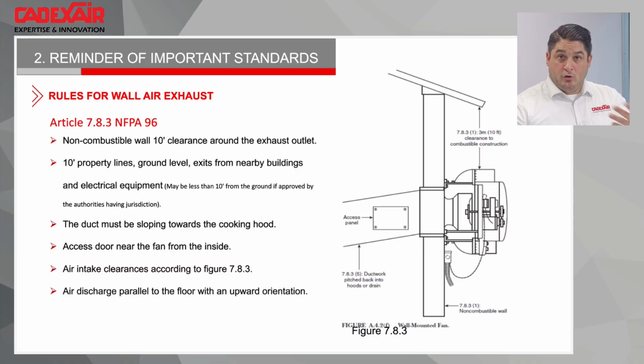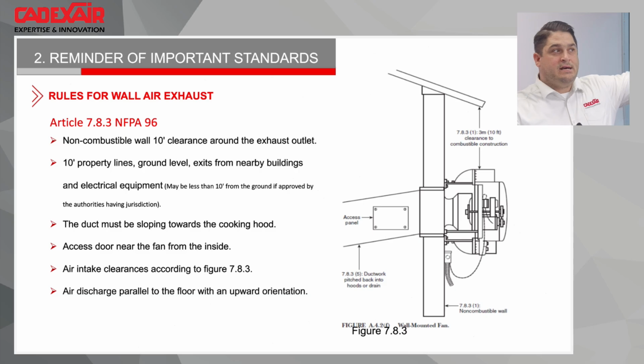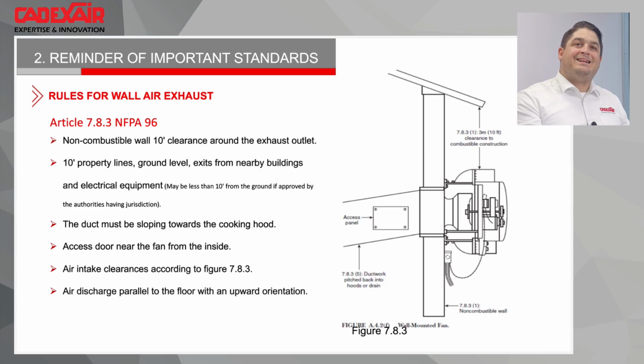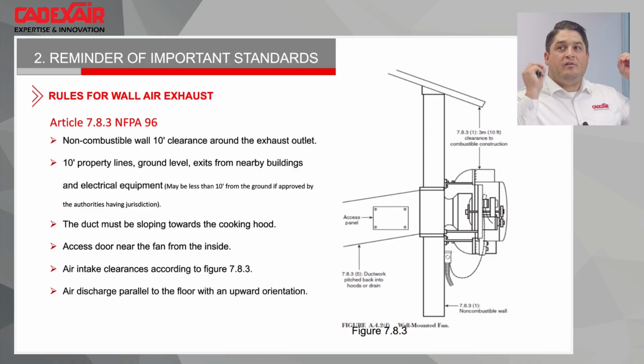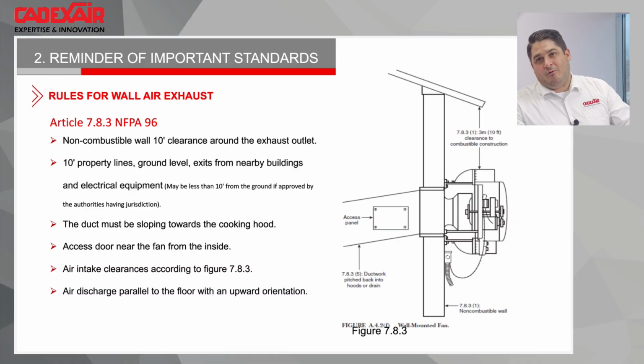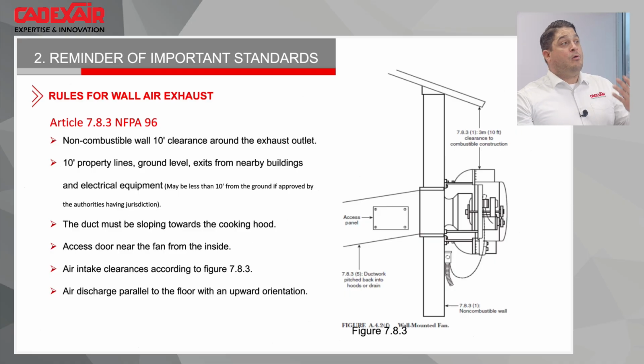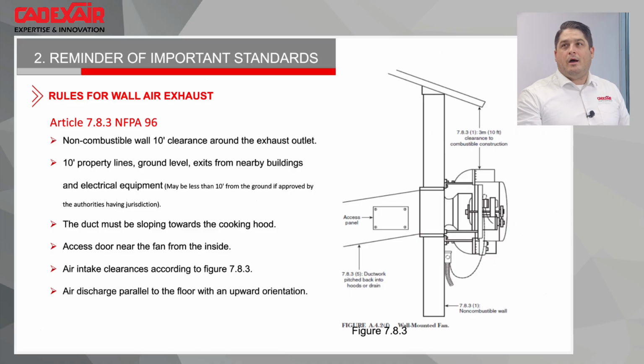Also, when you work with a louver on a wall discharge, you need to exhaust parallel to the floor or upward. Often we see exhaust flowing downward, and I understand it's so the louver will not let the rain in, but you push all the fire, the smell, and a bit of dirty air onto the people down the street. So you're supposed to shoot upward. Often when you have to exhaust on a wall, it could be a problem because you are in a high density area, and as soon as you shoot higher in the air, you get better dispersion of the smell and everything.